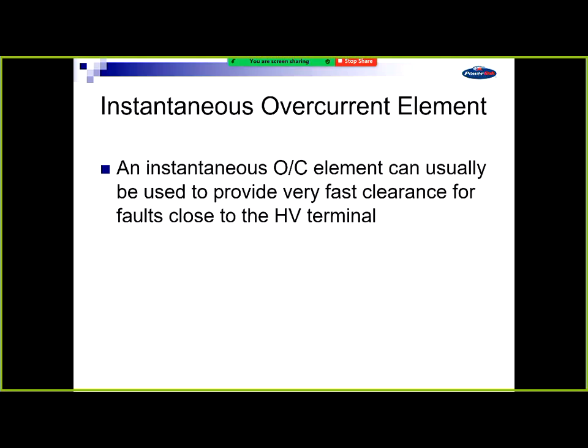So you can discriminate your HV terminal faults from your LV faults just on current, and that's where you can set it instantaneously. If that was the case, you set it to 8,000 amps primary and you trip instantaneously. You're not going to trip for low voltage faults because they're a lower current. That's when you've got to start using your IDMT and grading over top of low voltage protection. But on the HV side, you're using current as the discrimination.